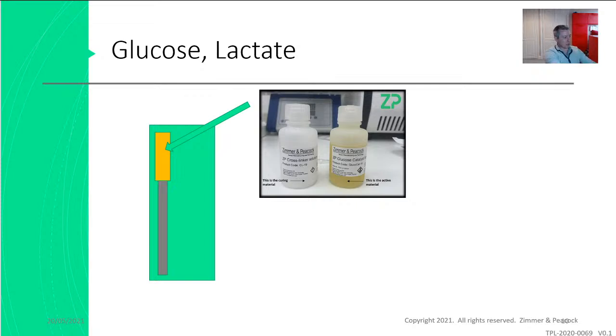But I think you can put these formulations onto a gold electrode. If there's any kind of hole in that gold electrode and the silver is coming through, you will definitely get an oxidation of the underlying silver, and you'll get a very large current, and it's not due to the glucose, it's due to the corrosion.